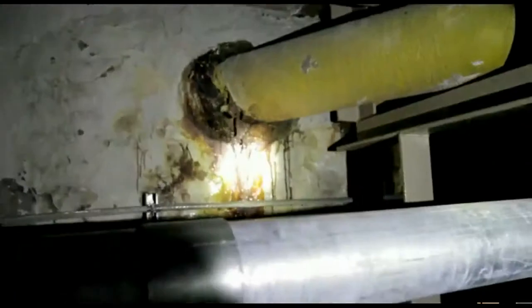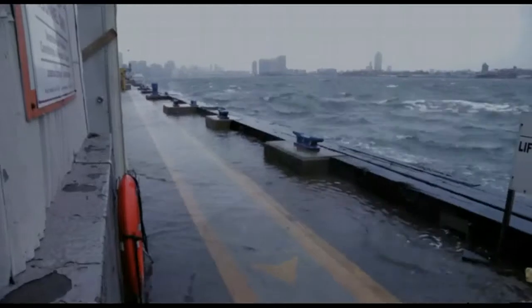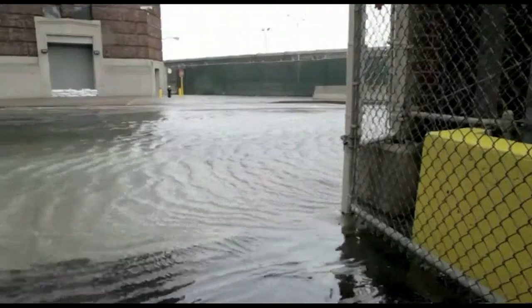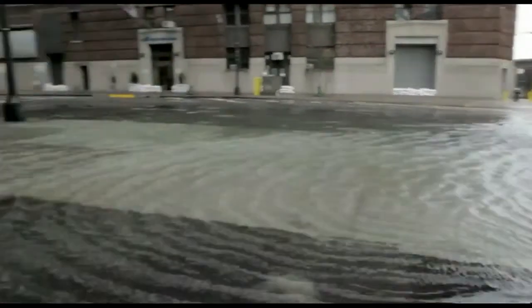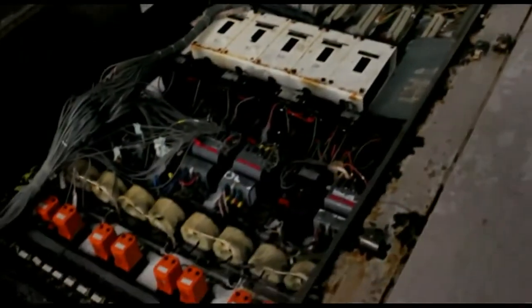The flashpoint was a circuit breaker that shorted out after the salt water rushed in. That breaker was at a lower elevation, and as the water rose, it flashed over and caused a subsequent failure at the transformer. You saw this big flash of light, then a cascading failure because of the other relays, and the station ended up being shut down.